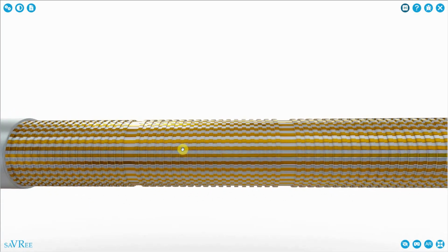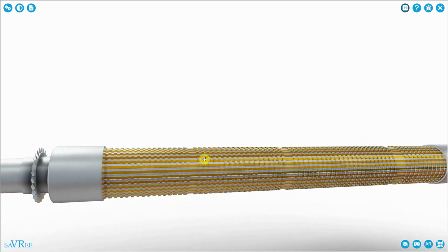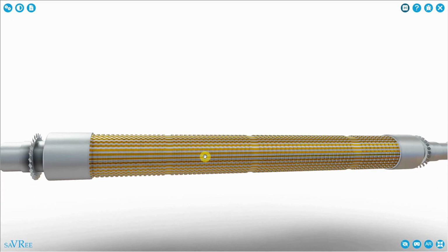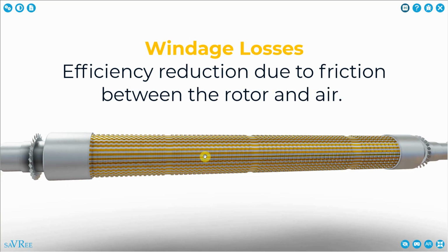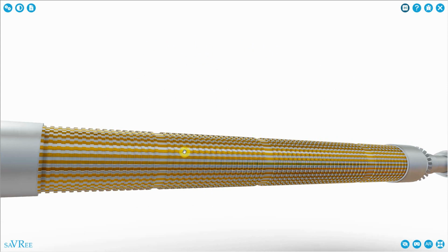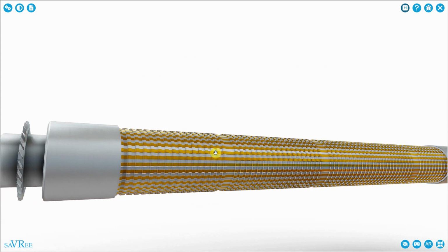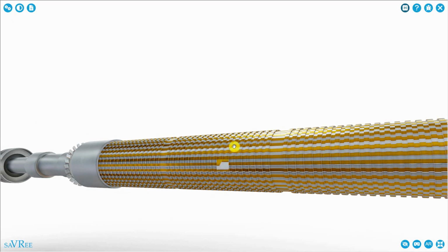My general thoughts are though that because the rotor is rotating at such high speeds, these grooves are not desired. The rotor encounters resistance as it rotates, and we want to minimize this. For this reason, I would expect the rotor surface to be smooth. However, I have not seen every type of generator rotor that's ever been designed, so I'm just trying to use my engineering powers of deduction here to figure out why it may have these grooves.